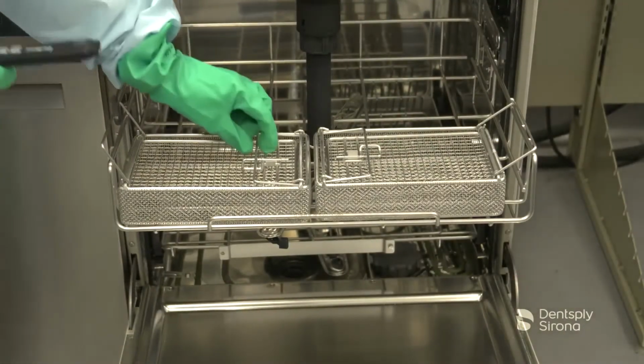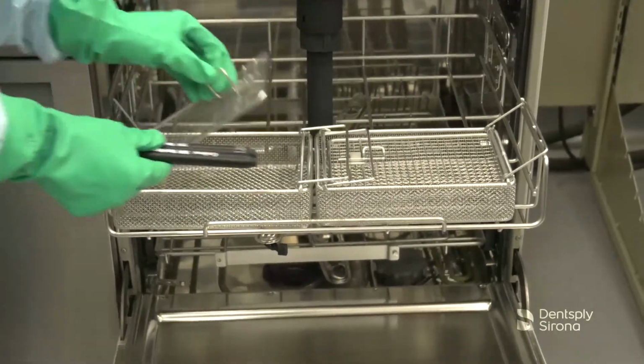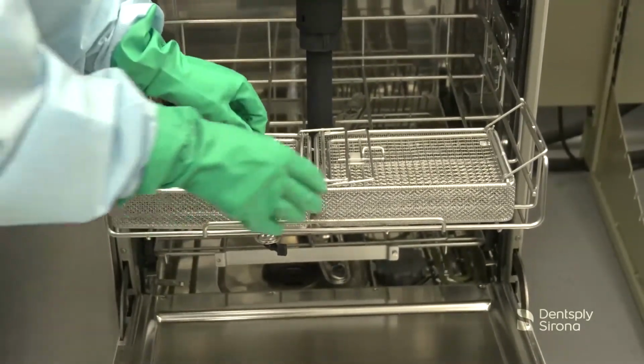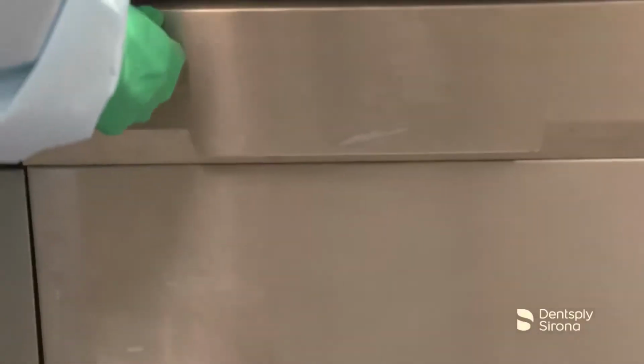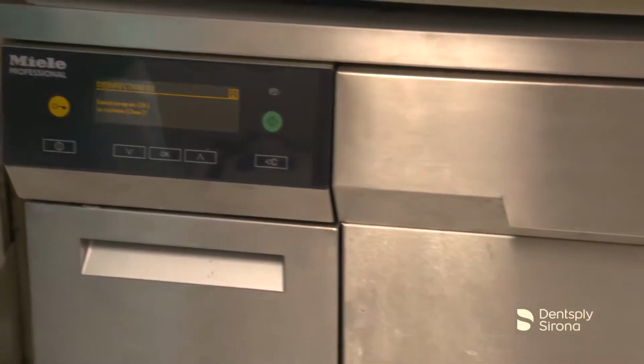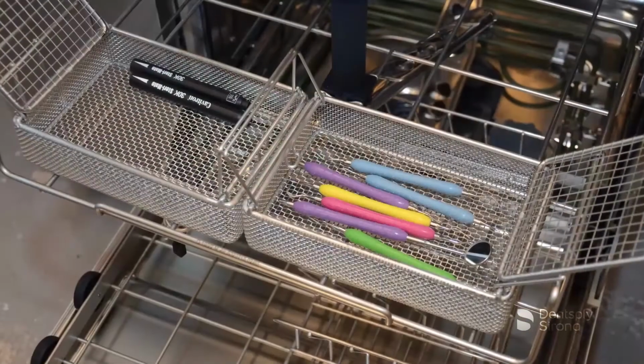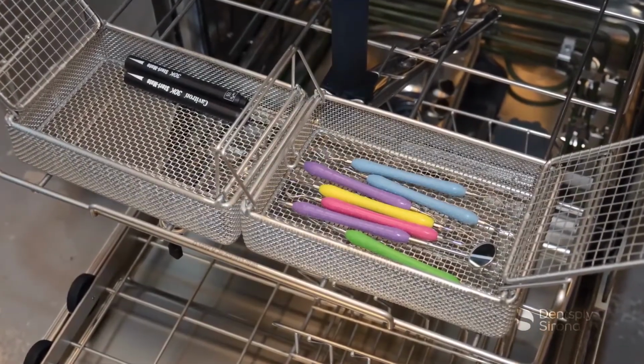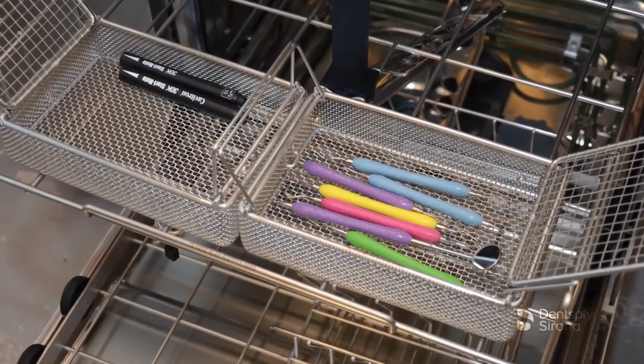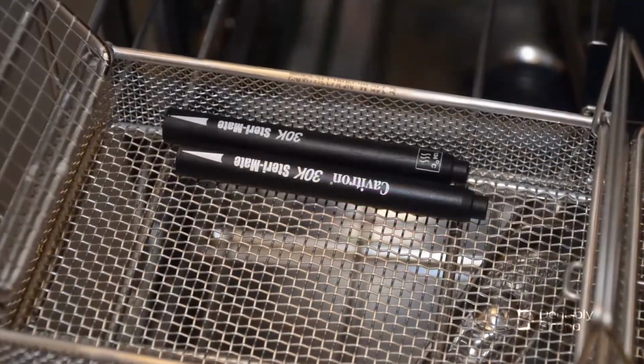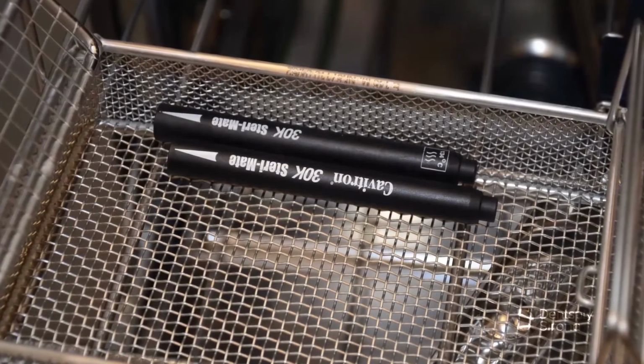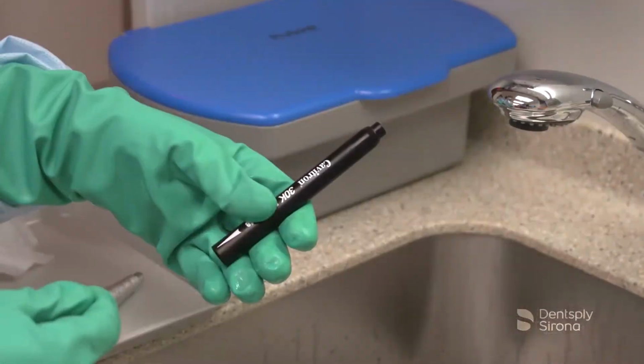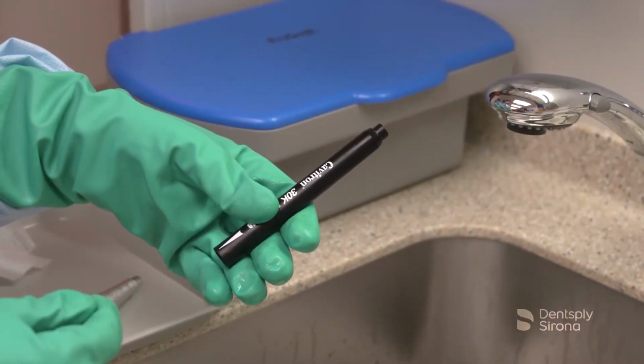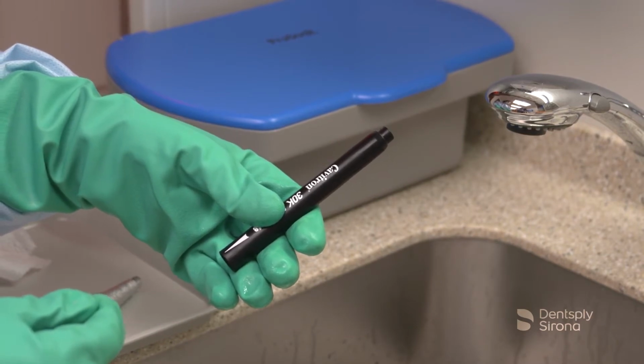Steri-mate handpieces can be cleaned and disinfected in automated instrument washers. For cleaning and disinfection of these handpieces in an instrument washer disinfector, always follow the manufacturer's instructions for use for the unit and the instrument washer solution, making sure to observe the concentration rates and contact times, as well as the instrument washer's recommended cleaning and/or thermal high-level disinfection cycle. After the dry cycle is complete, always inspect for remaining debris. If debris is still visible, repeat the washer disinfector cycle.